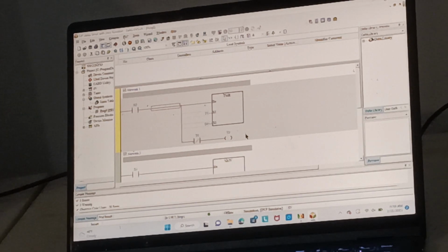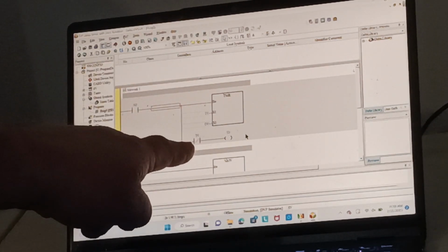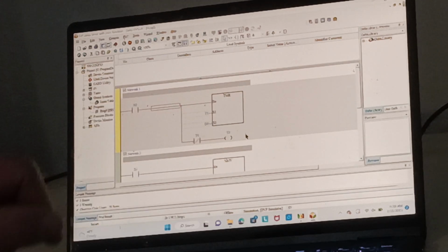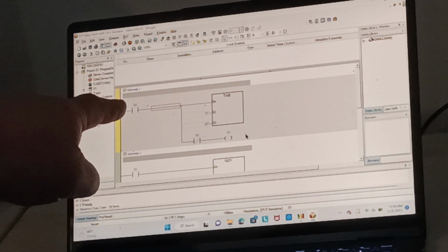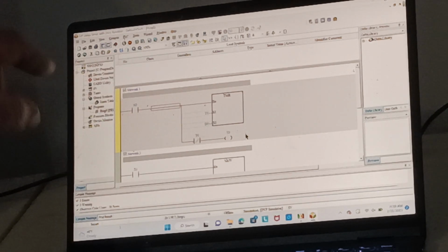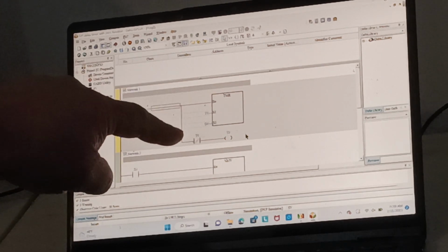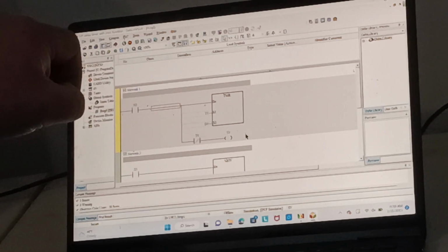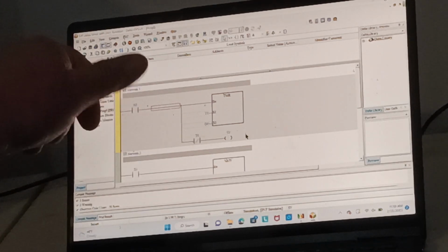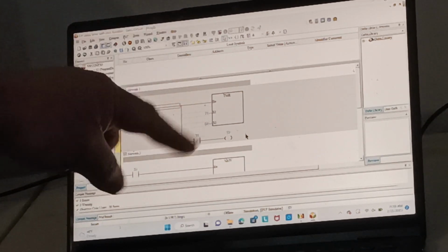Okay, right here what we have is a basic off delay timer. You'll notice the last timer, if you need to rewind it, basically looks the same. The only difference is we have a normally closed contact here. So when we hit our input X0, when the sensor senses whatever that input is, it'll start my timer. Whereas the on delay timer was a normally open contact and it closes when it reaches its set time, this is closed and it stays closed until the timer reaches its set time, then it opens. So this is an off delay timer.